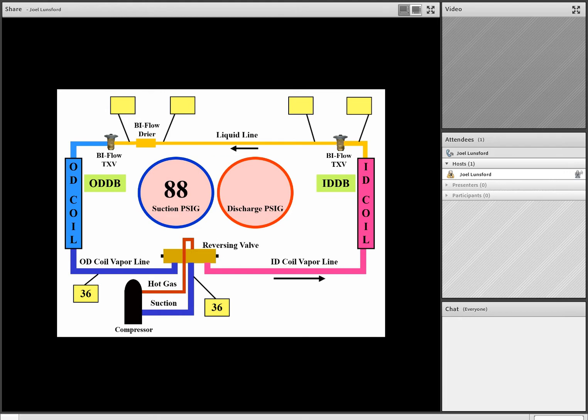normal range. Remember, team, in the heating mode, there's a much broader range on superheat because the outdoor coil can start to ice up under cold conditions. So about 4 to 15 would be considered normal in the heating mode of operation. And so in our example, we have approximately 11 degrees of superheat. The outdoor coil in this example would be considered normal.